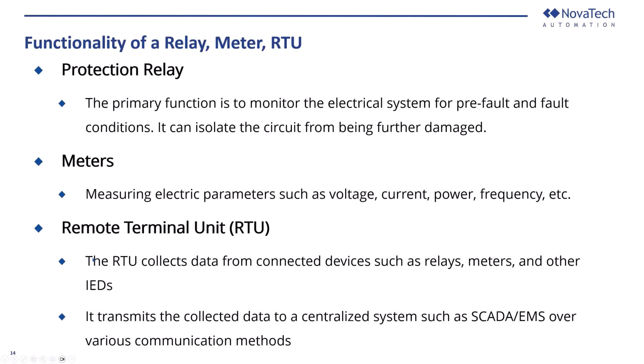The third component we have is the RTU. We touched base a little bit on the RTU - different people call it differently, some call them gateways, data concentrators, or RTUs. The primary goal of the RTU is to collect data from connected devices, such as relays, meters, and other IEDs from the substations, and then transmit that collected data to a centralized system, such as SCADA or EMS, over different communication methods that we discussed before. Now we will look into each of these components in depth.